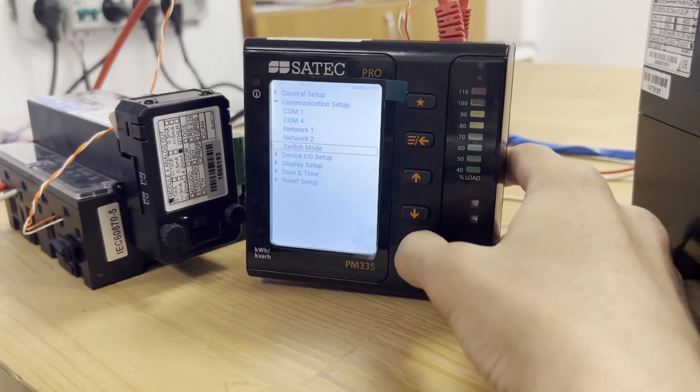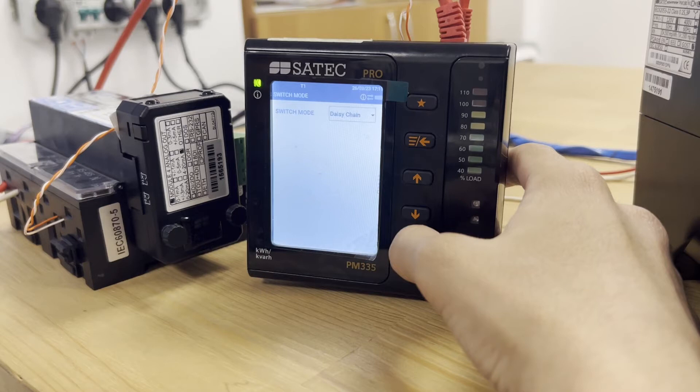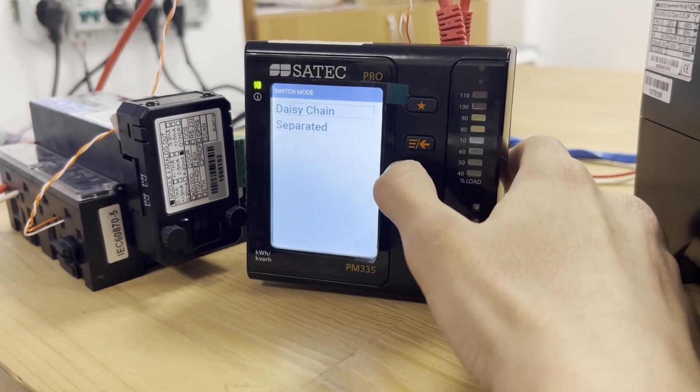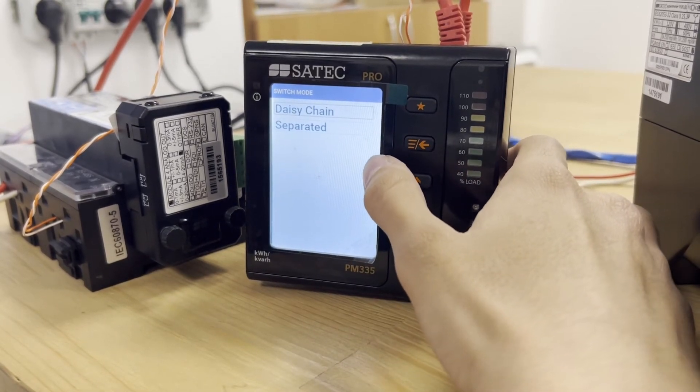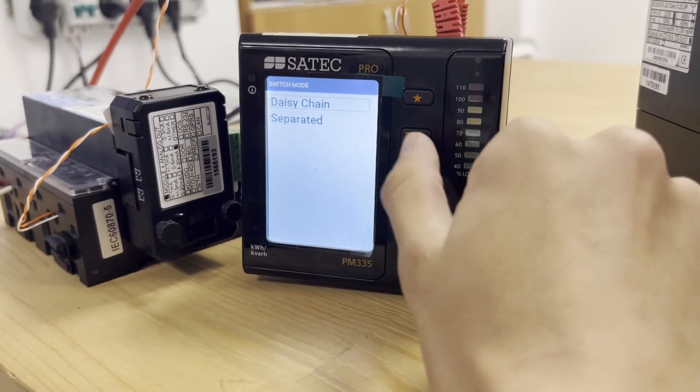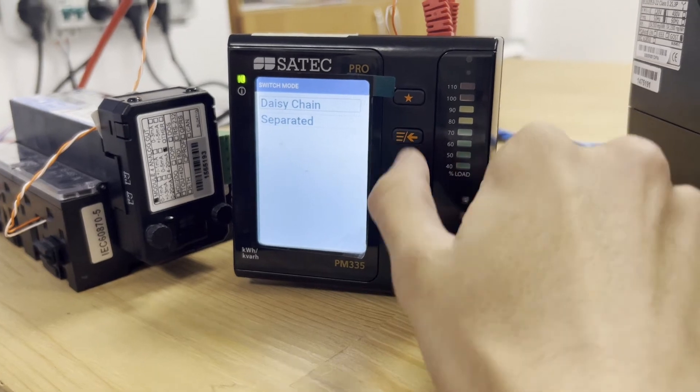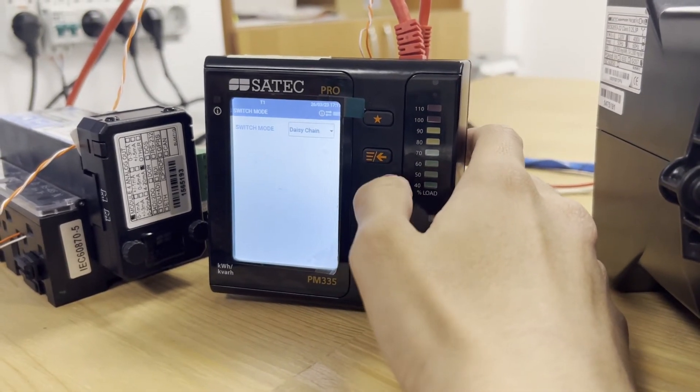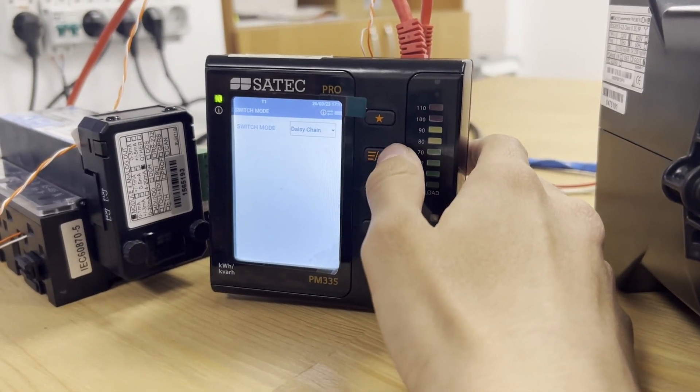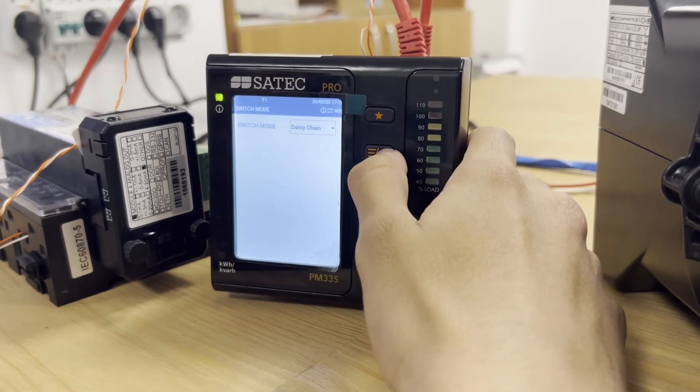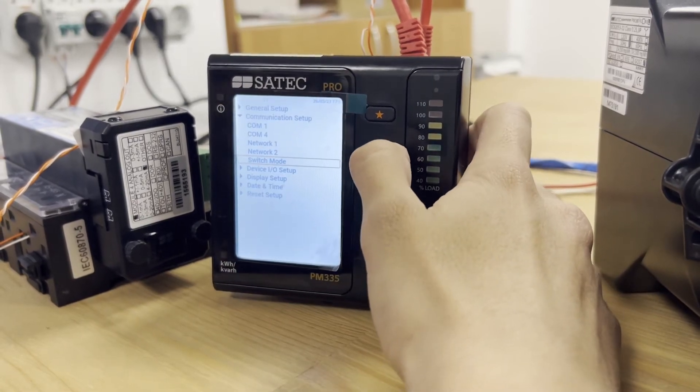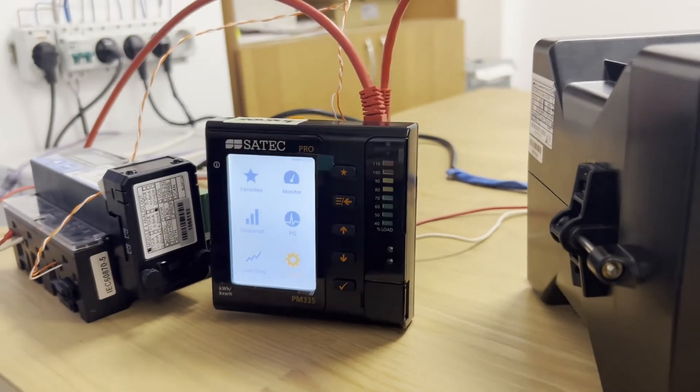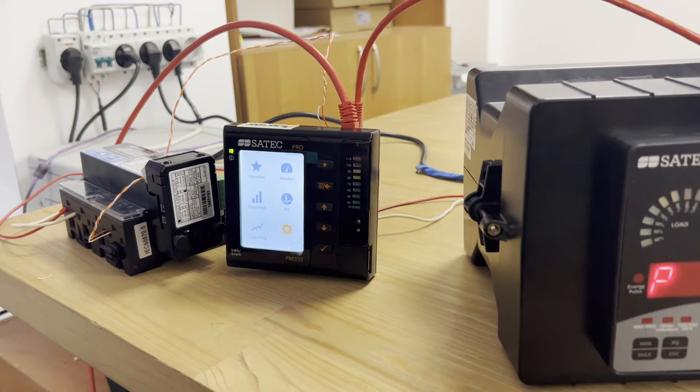And we need to go to the switch mode. For correct polling of the device from both ethernet ports, we need to select daisy chain. Separated mode separates both interfaces. This mode is mainly used for transferring data to different systems.